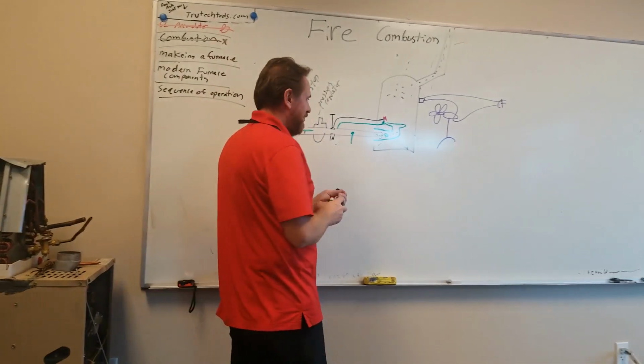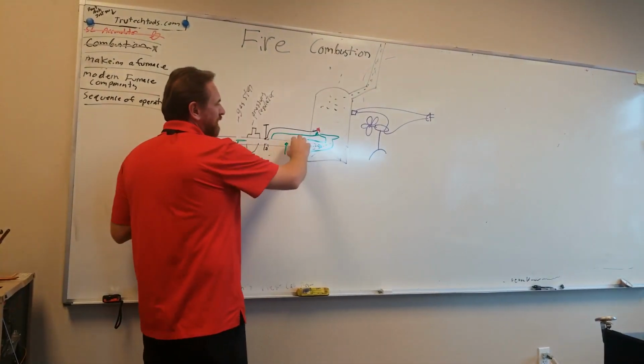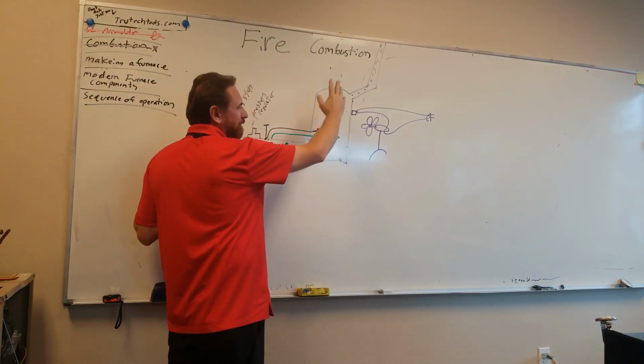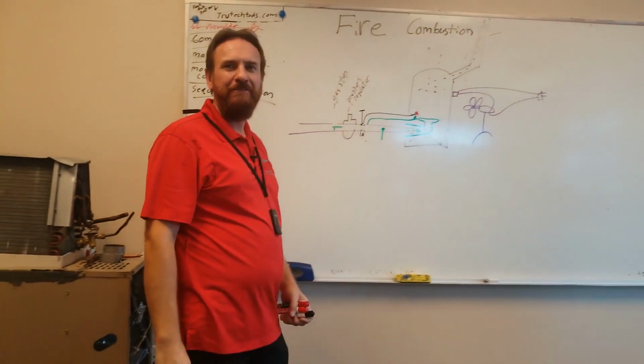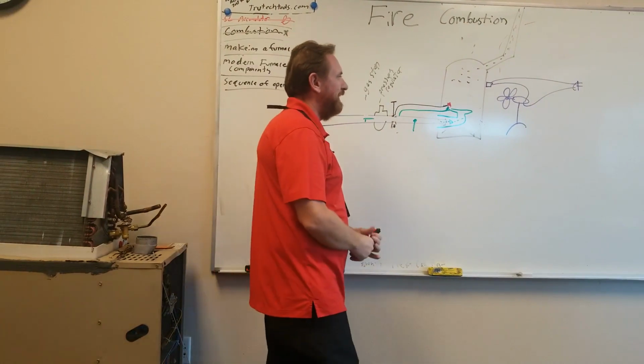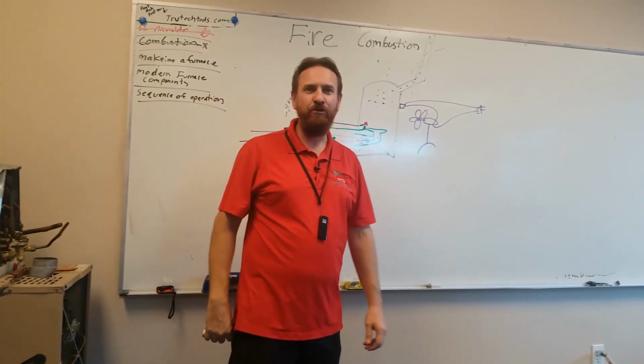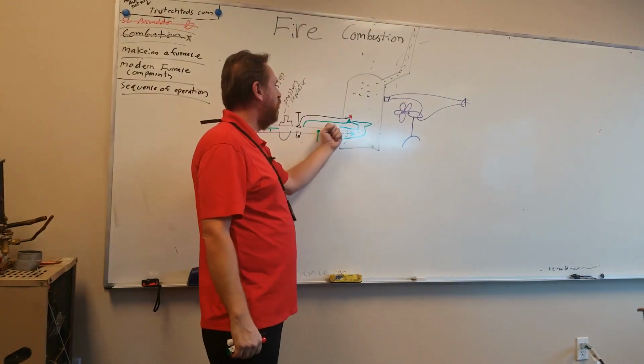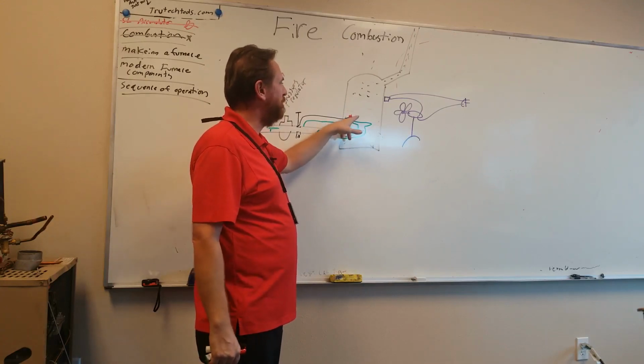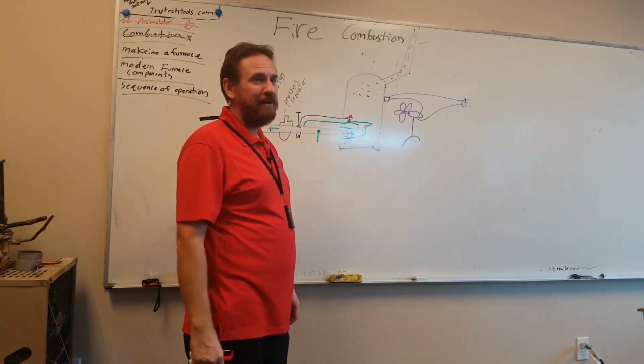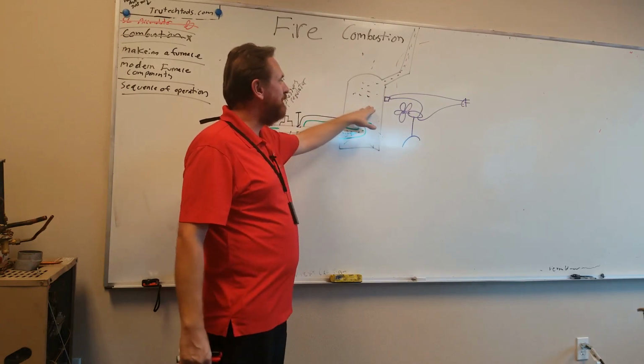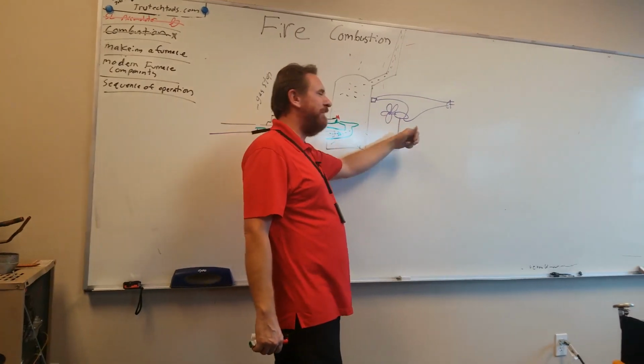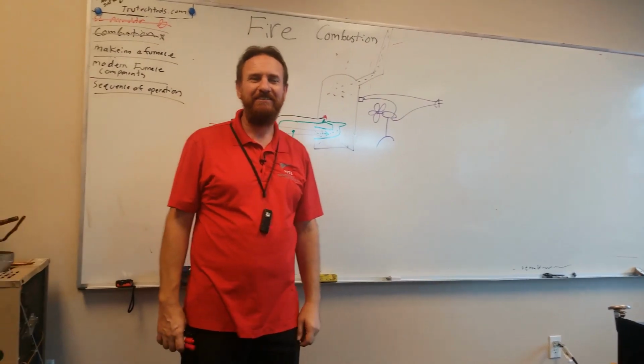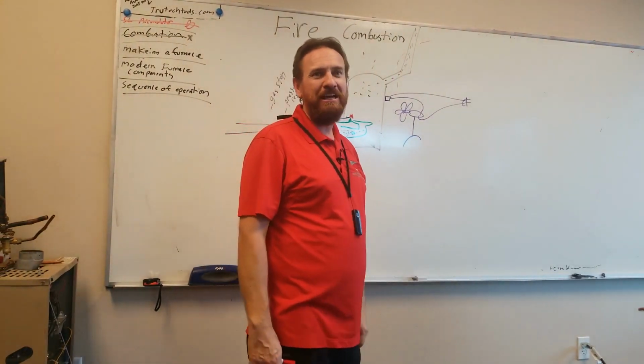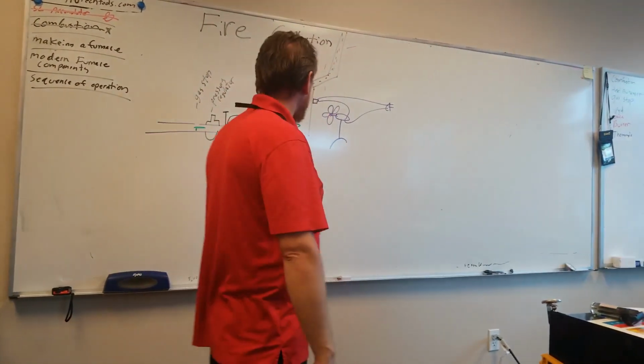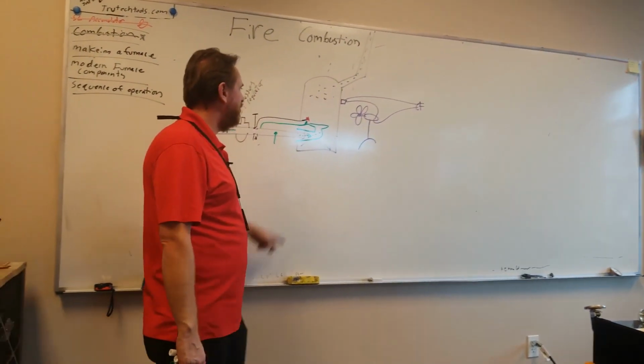Okay. So now when I open this valve, gas flows through here, across the light, ignites into a flame. Life is good. So now all I got to do, middle of the night, it gets cool, I just run downstairs. I open this valve. Gas flows in here, across the pilot, burns into a flame. Go back to bed. As soon as that heat exchanger heats up, this switch closes, brings on the fan, starts moving air into the house. Then, wake up in the middle of the night, a few hours later, it's hot in the house, run back downstairs, I close this valve off, the pilot stays on.